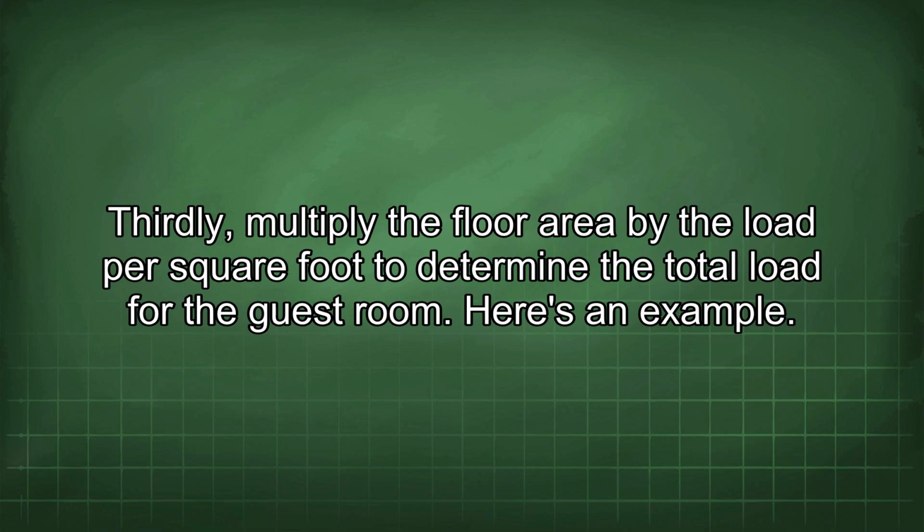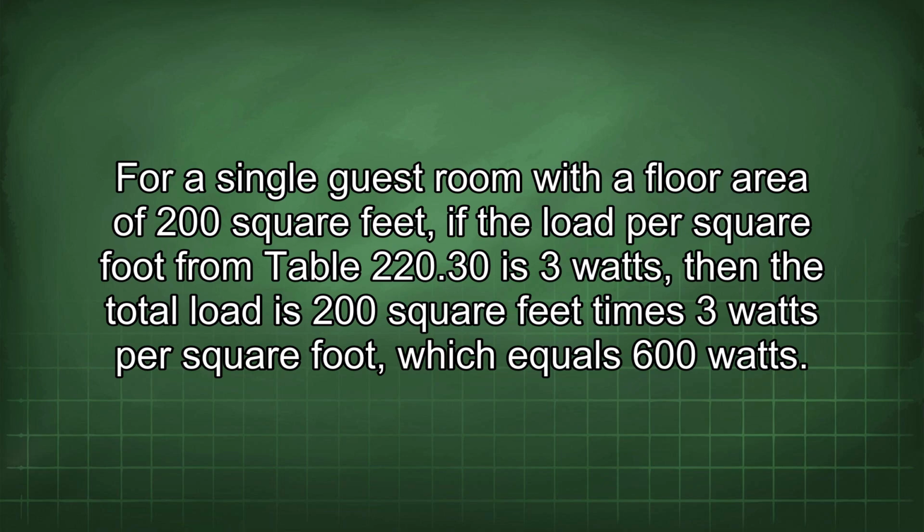Here's an example. For a single guest room with a floor area of 200 square feet, if the load per square foot from Table 220.30 is 3 watts, then the total load is 200 square feet times 3 watts per square foot, which equals 600 watts.